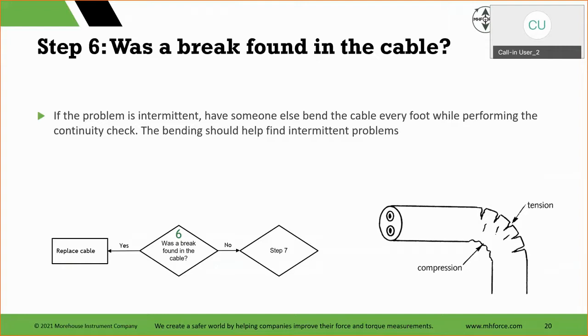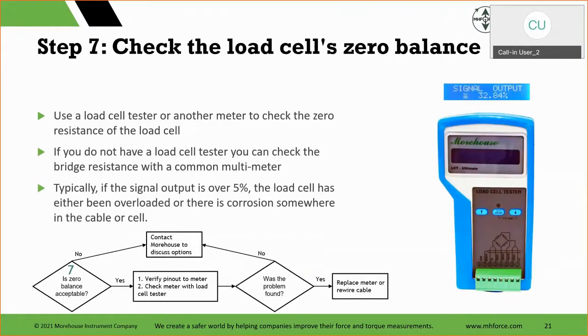And it starts kiting because guess what? When you randomize the connections, you move the cable that you had previously supported during the cal. Check the load cell's zero balance. Cannot stress this enough. If you have a meter, some meters you can just plug the load cell into and check them. Check an unbalanced zero.